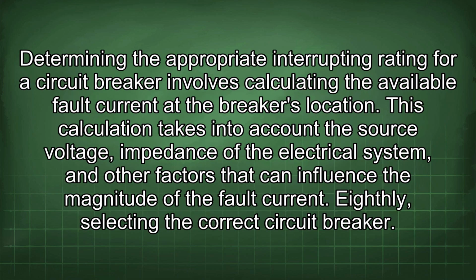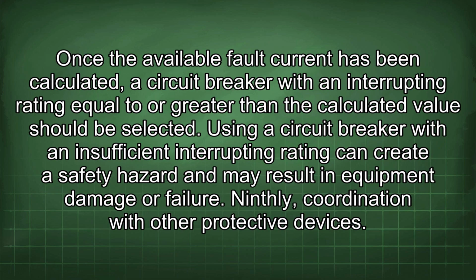Seventhly, fault current calculations. Determining the appropriate interrupting rating for a circuit breaker involves calculating the available fault current at the breaker's location. This calculation takes into account the source voltage, impedance of the electrical system, and other factors that can influence the magnitude of the fault current. Eighthly, selecting the correct circuit breaker. Once the available fault current has been calculated, a circuit breaker with an interrupting rating equal to or greater than the calculated value should be selected.